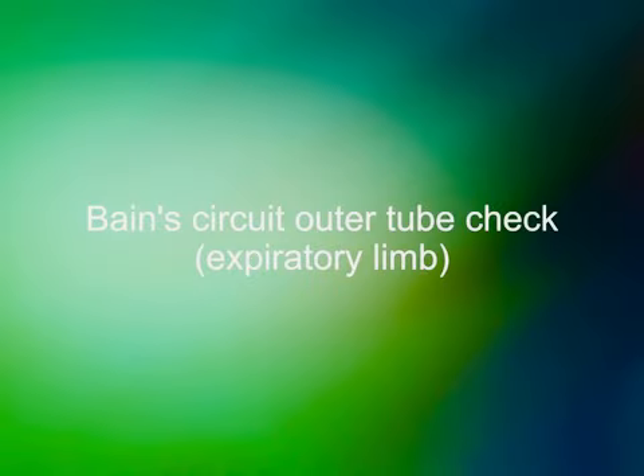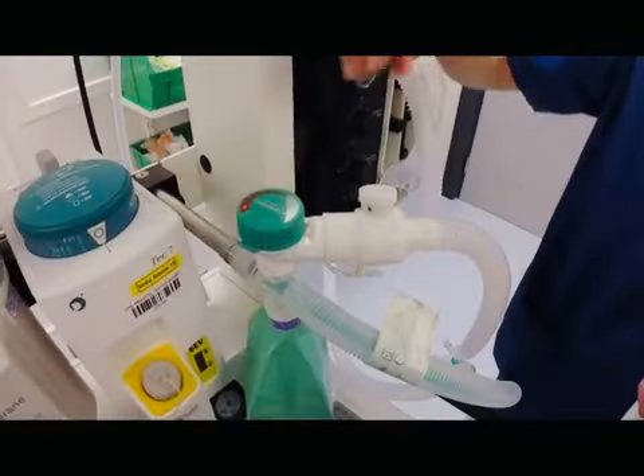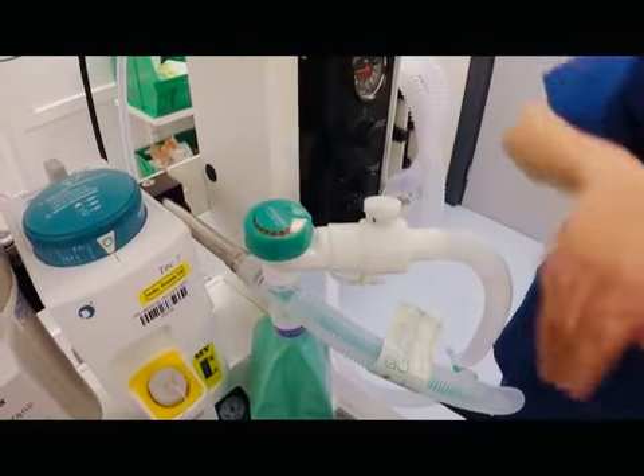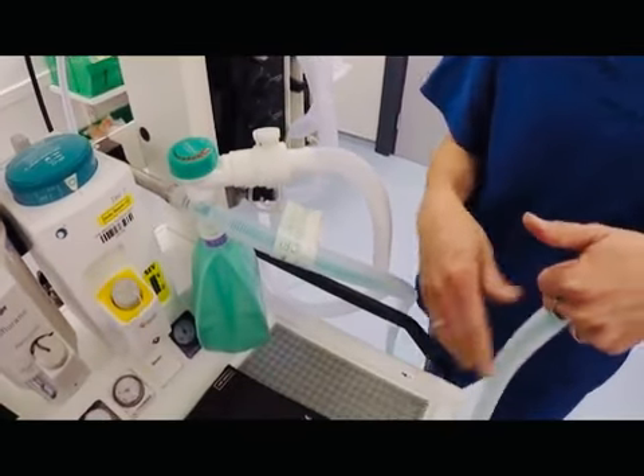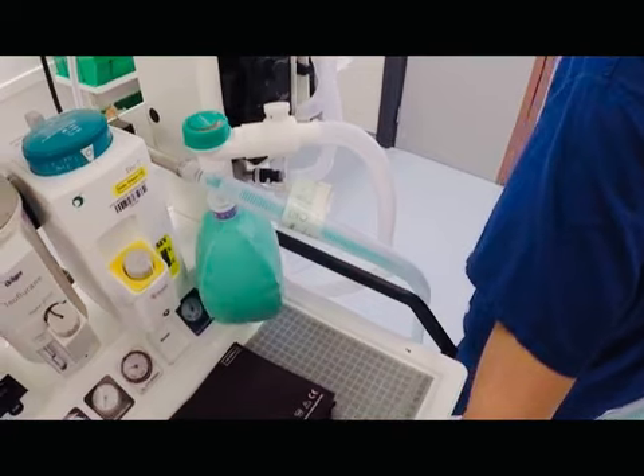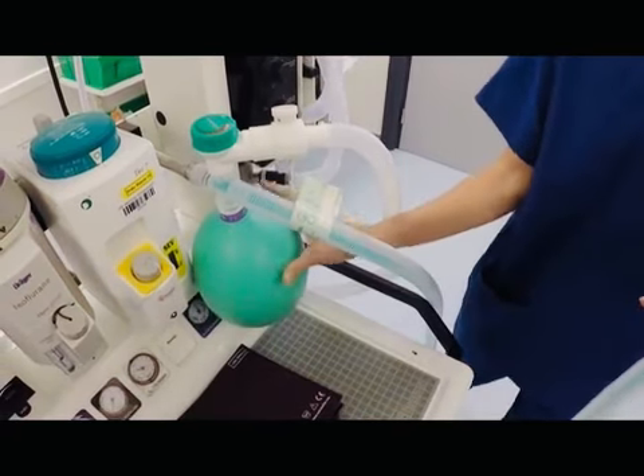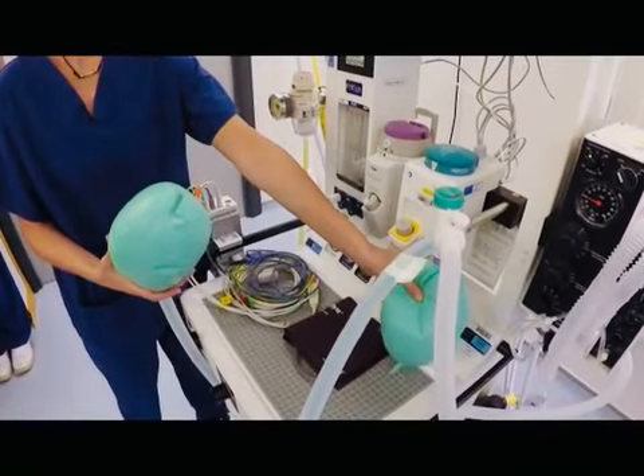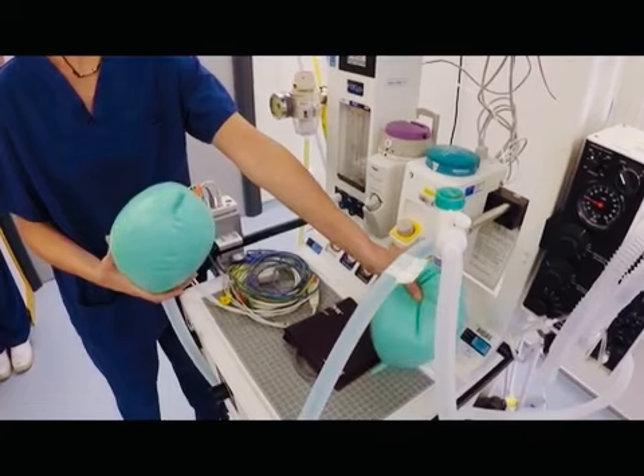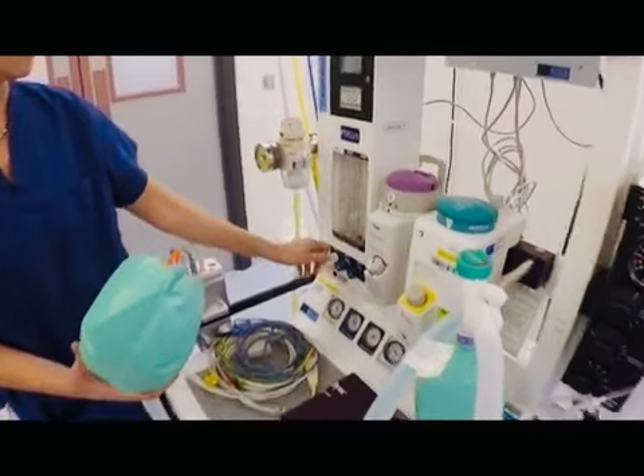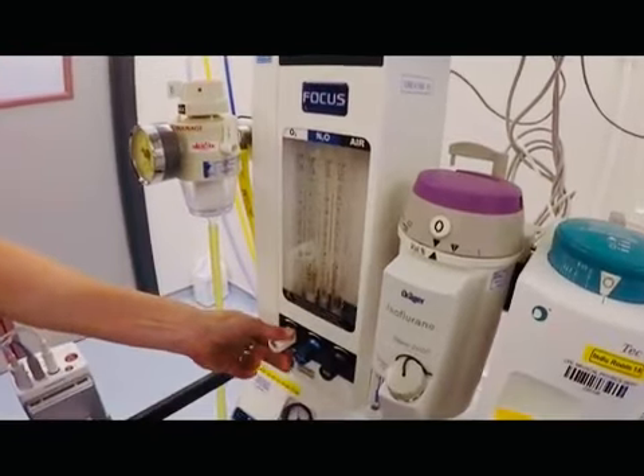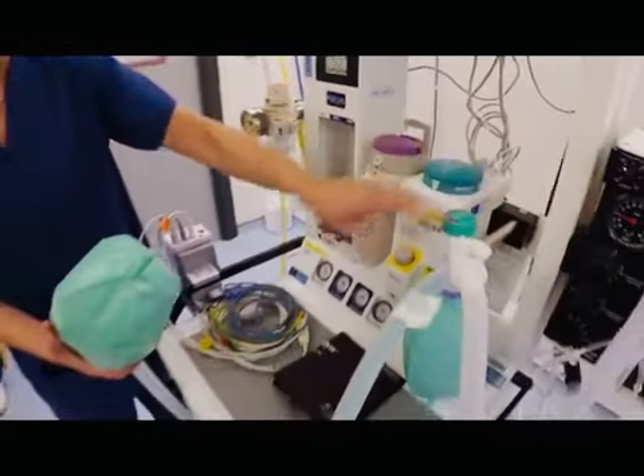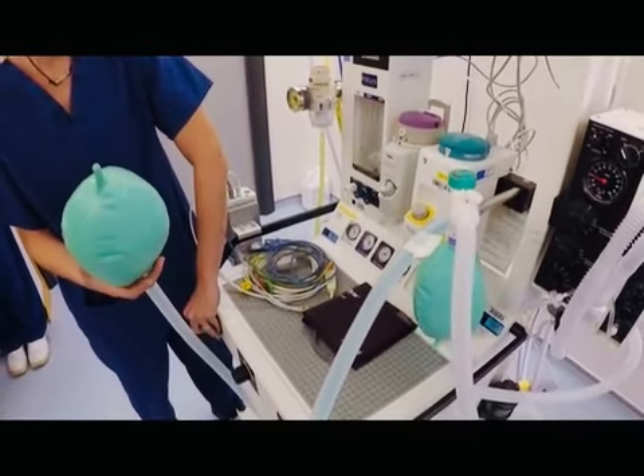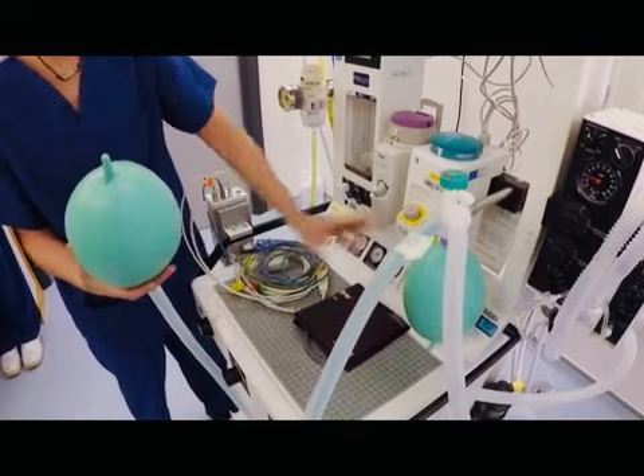The outer limb, running from the tip back to the bag and the APL valve, also needs to be checked. Close the APL valve fully and occlude the tip so that the bag fills without emptying. For a double bag test using a Bain circuit without ventilator and with the oxygen at 5 litres per minute, close the APL valve so that it is half open, using a second bag as a test lung, so that squeezing the bag on the Bain circuit will fill the bag attached to the tip. Now close the APL valve fully and switch off the oxygen. Squeeze both bags to ensure no leak.